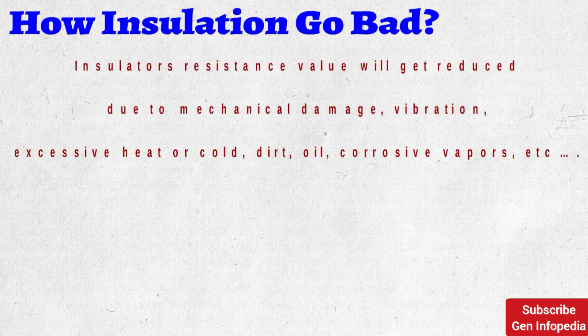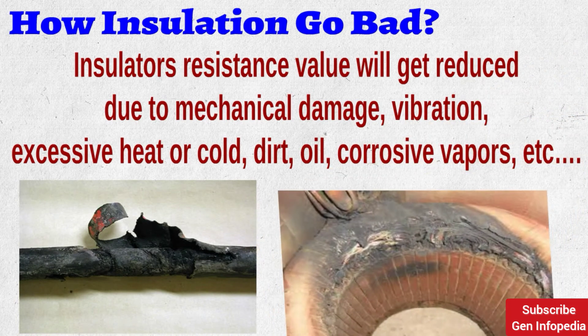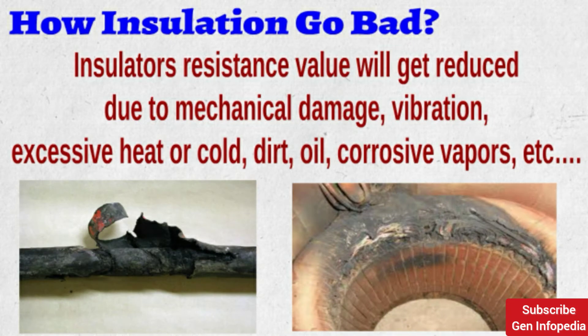How does insulation go bad? When your electrical system and equipment are new, the electrical insulation should have high resistance. But over time, this insulator resistance value gets reduced due to many reasons — mechanical damage, vibrations, excessive heat, dirt, or corrosive vapors. In those conditions, small pinholes or cracks develop in the insulation, and moisture and dust penetrate the surface, providing a low-resistance path for leakage current. Insulator resistance usually drops gradually, giving warnings, so we need to check insulation resistance periodically to prevent equipment damage.